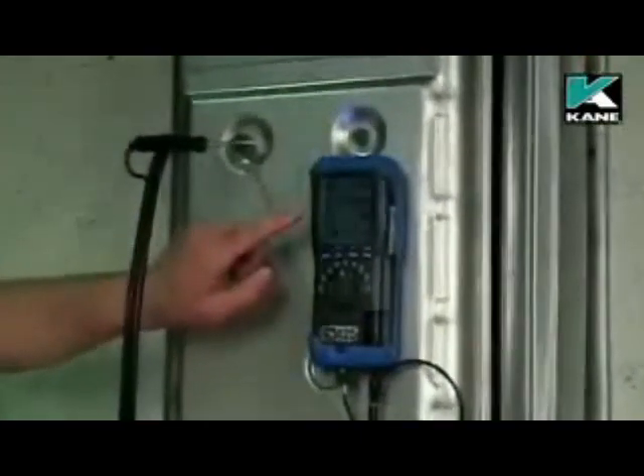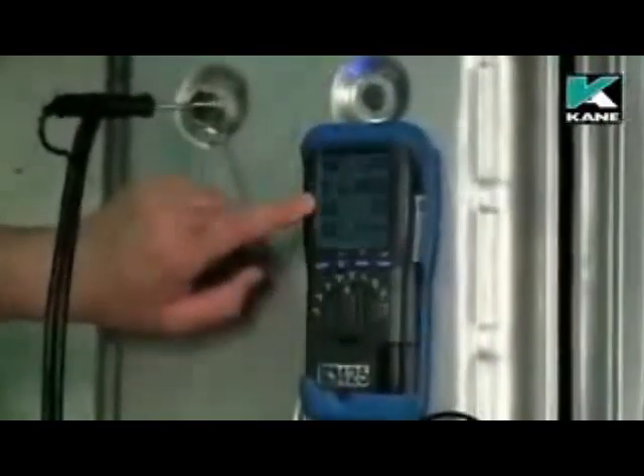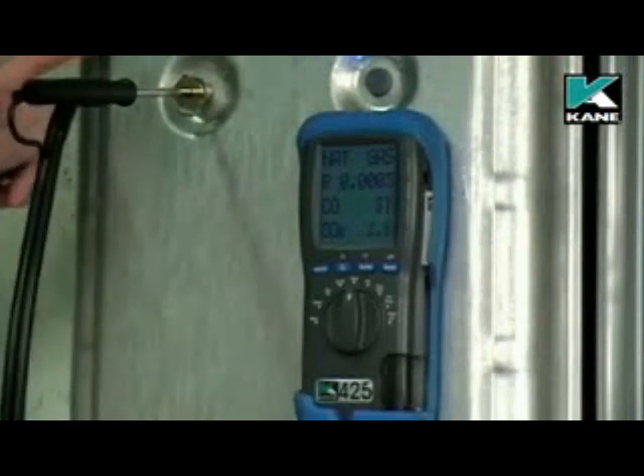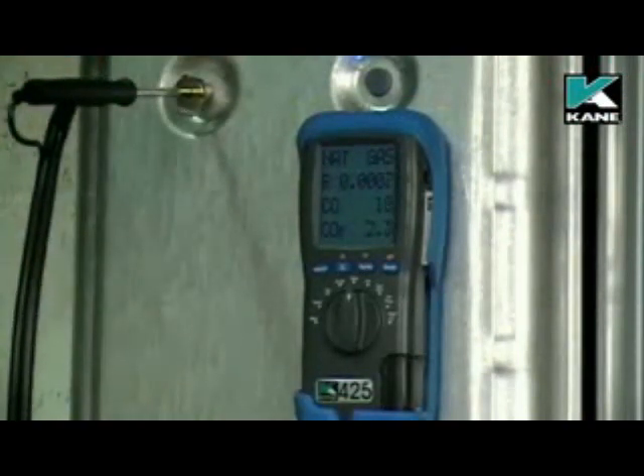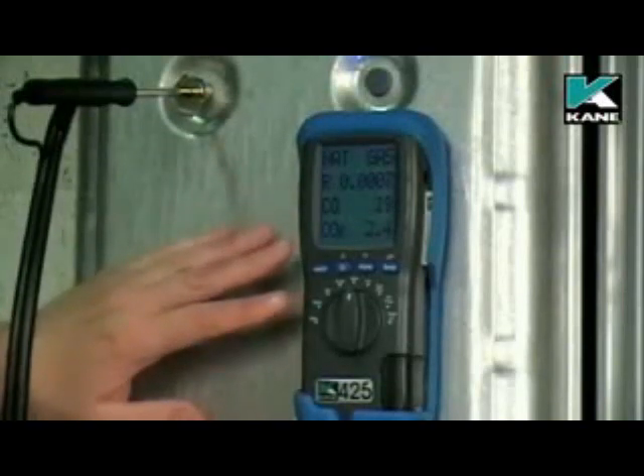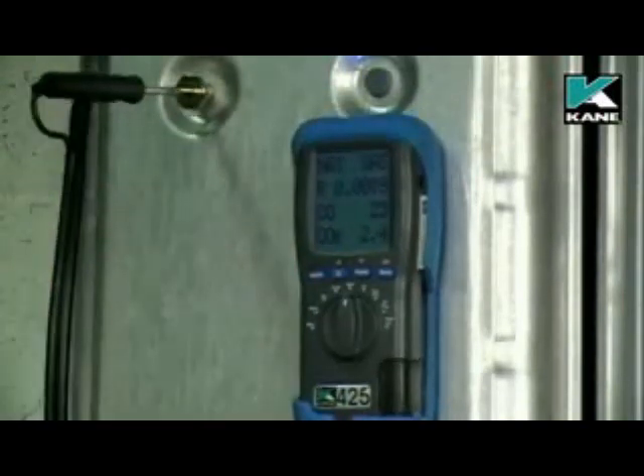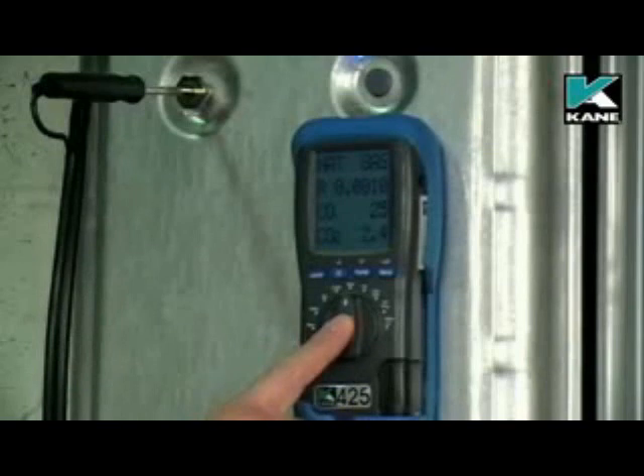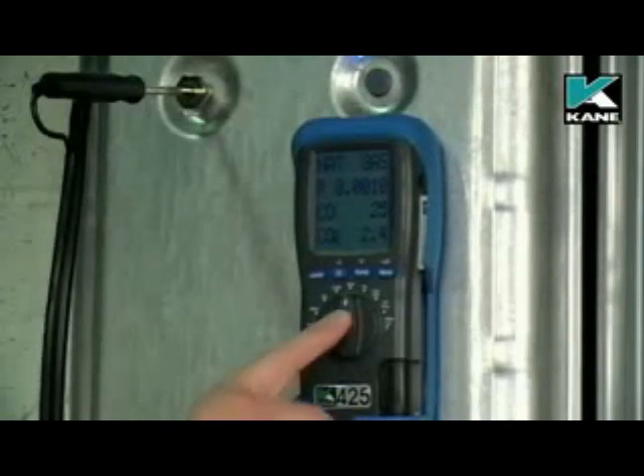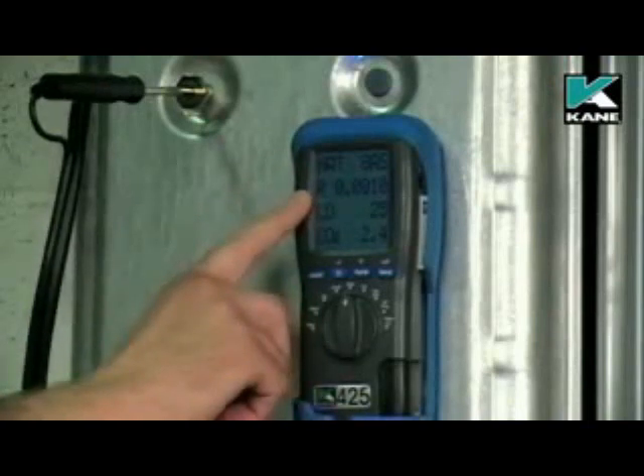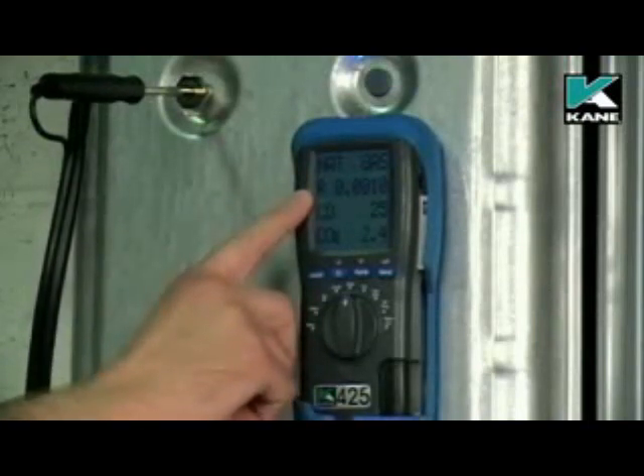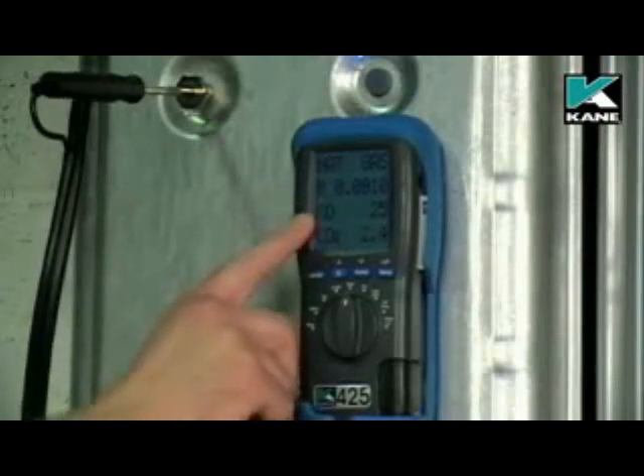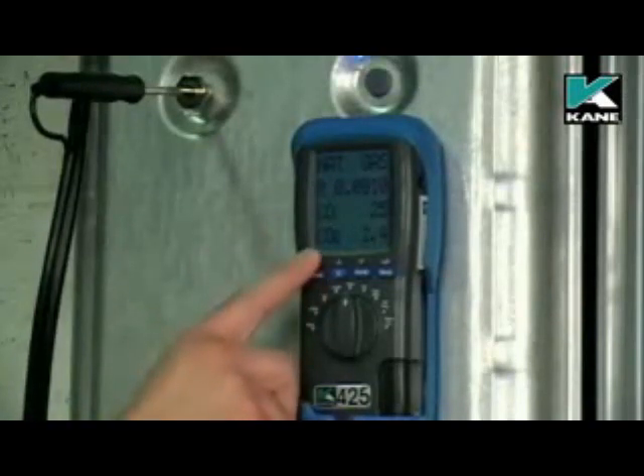Now you'll notice that the readings have about a 10-second delay. This is the time for the sample of flue gas to actually travel the length of the hose and be analysed. It is actually continuously sampling. When the readings have stabilised, typically after a minute or so, with the dial in the ratio position, you can check the actual CO/CO2 ratio to 4 decimal places, the carbon monoxide readings in parts per million, and the carbon dioxide or CO2 reading in a percentage.